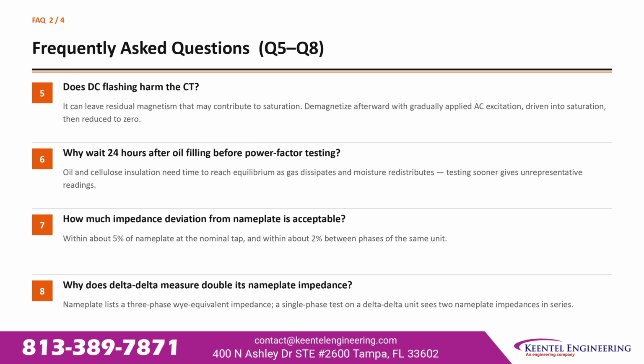Why wait 24 hours after oil filling before power factor testing? Oil and cellulose insulation need time to reach equilibrium as gas dissipates and moisture redistributes. Testing sooner gives unrepresentative readings.